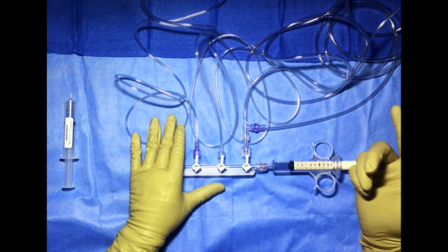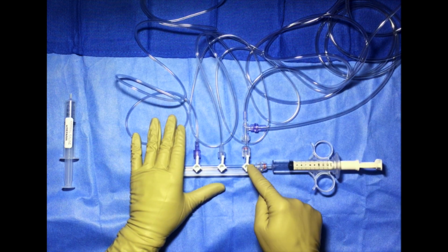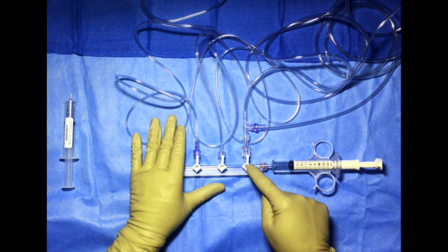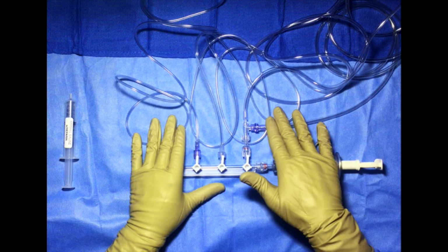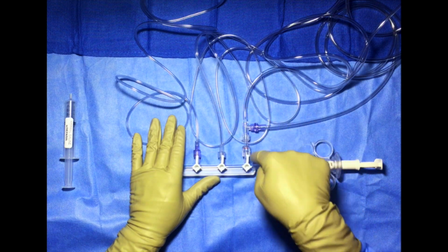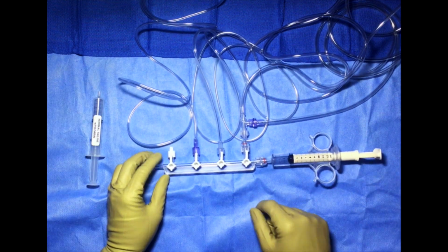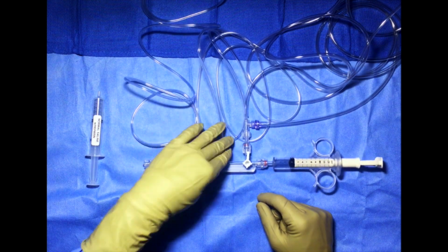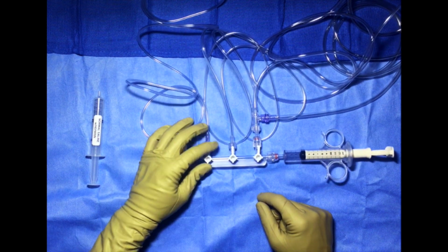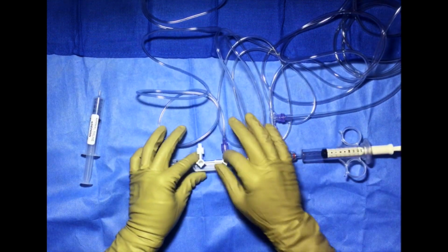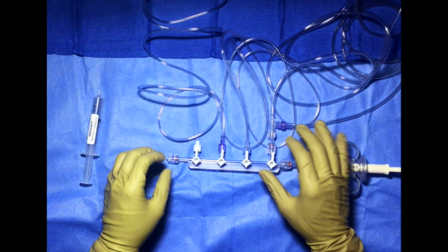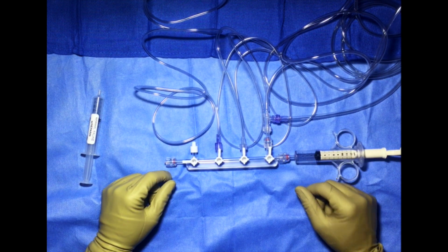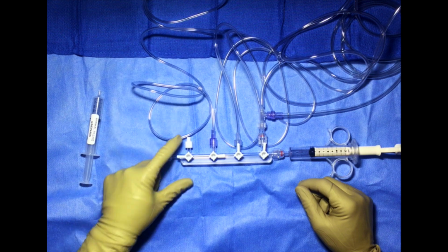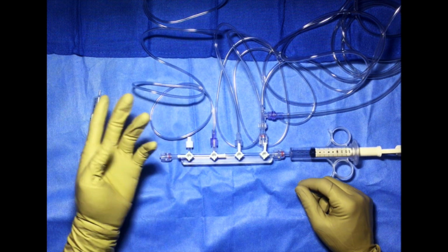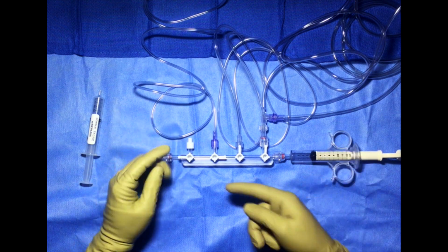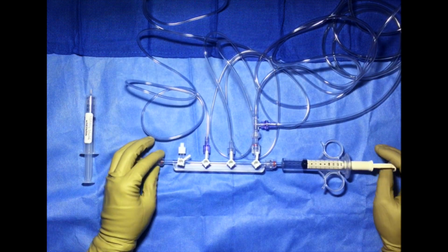contrast, saline, waste, or these two could be flip-flopped and your contrast would be closer. I believe they're always going to put the waste closest to the syringe if there is a waste bag, because you don't want to be pushing waste in between any other connections. Again, just think about where the stuff goes. This is contrast, so nothing's going to happen until I pull. This is saline under pressure, so if I go here, it's going here. If I go here, it's going there. It's going out. If I do this, I got nothing. I mean, I could open this arm on, and it's hard to tell because there's not a cap on there to keep fluid from going out, but really nothing's going to happen there. When we use fluids, it's easy to figure out how to do.